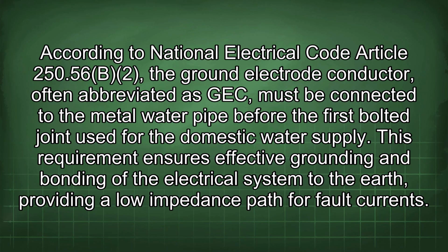According to National Electrical Code Article 250.56(B)(2), the grounding electrode conductor, often abbreviated as GEC, must be connected to the metal water pipe before the first valve or joint used for the domestic water supply.